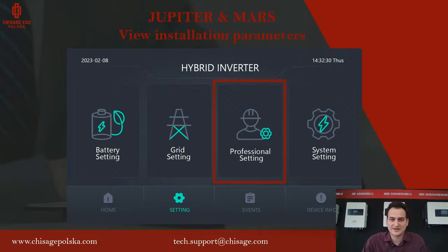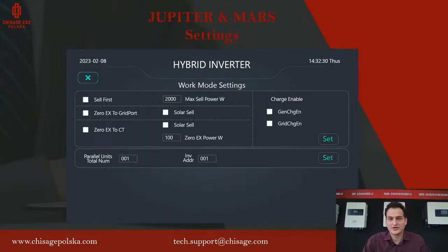Fourth settings are professional settings. Here we set up the working mode of the inverter on the left. On the right, we have the grid and gen charge enable. So we allow the grid charge or we allow the gen charge or we don't. And at the bottom, we have the parallel settings. So we put how many units in total we have connected in parallel, and the inverter address.